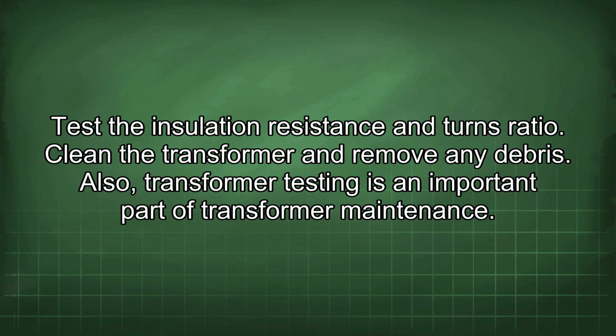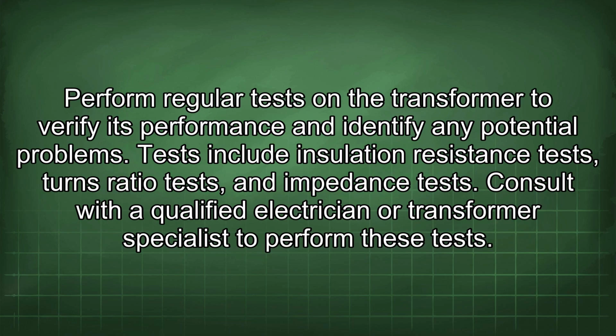Also, transformer testing is an important part of transformer maintenance. Perform regular tests on the transformer to verify its performance and identify any potential problems. Tests include insulation resistance tests, turns ratio tests, and impedance tests. Consult with a qualified electrician or transformer specialist to perform these tests.